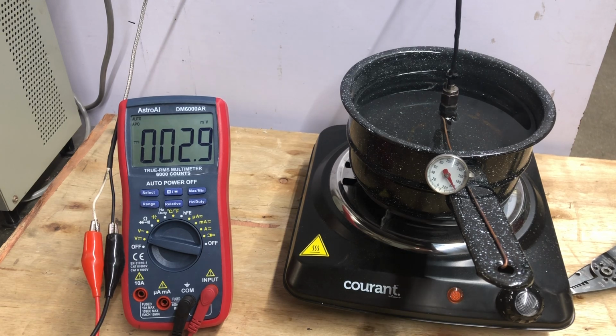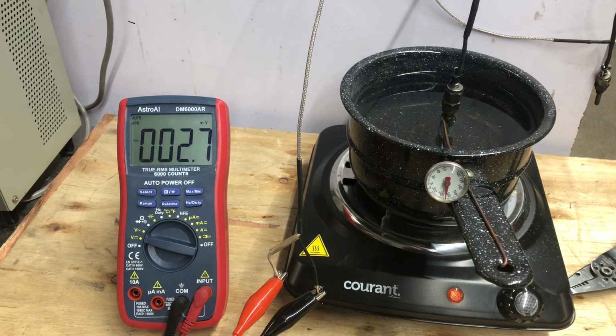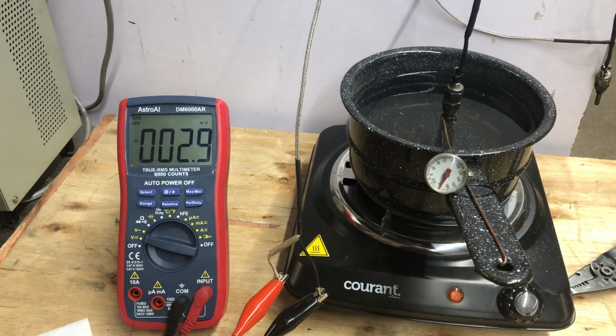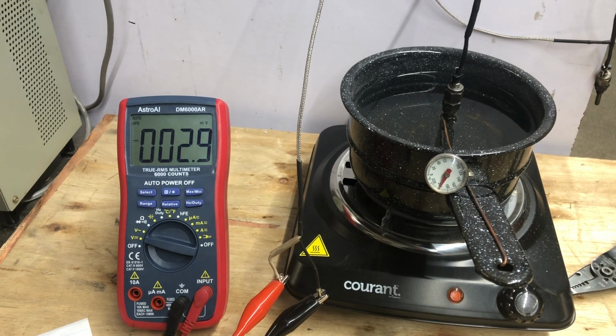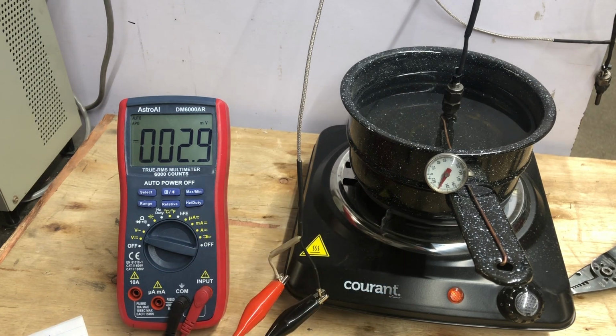So now I'll switch over, we'll check the other one and see if it's the same way. So I've just switched over to the other probe now, and the water has cooled down. It's about 185 or 186. And we'll let it warm up and see what we get when it hits 200. Now this just hit 200, and I have, as you can see, 2.9 millivolts, exactly the same as the other. So that's perfect. I'm really happy with that. So both of them check out with the ohms resistance when we did our ohms on them, and now at 200 degrees, they both check out exactly the same.